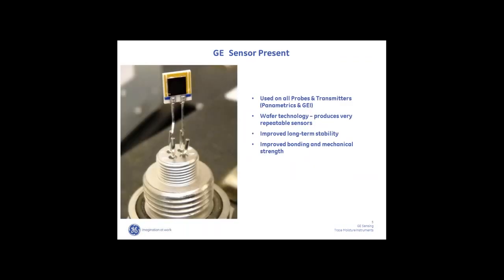After 2012 we went to a silicon substrate design where we make the sensor on a wafer. By coating the wafer with an aluminum oxide layer and then an overcoating of gold, we're able to make many of these sensors on a standard wafer, then slice up the wafer and mount them into our probe assembly. The wafer technology produces very repeatable sensors and gives us very good long-term stability, better bonding, and improved mechanical strength over the previous sensors.